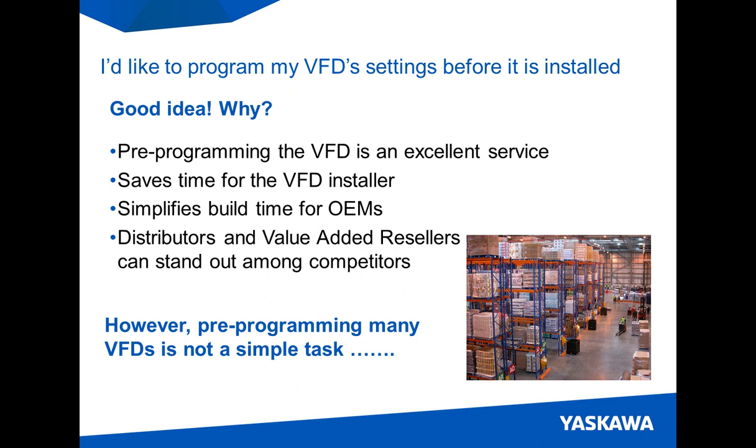So one of the things that I'm really excited to talk to you about in this next topic is a VFD, having hundreds of settings and parameters, making it capable of a wide variety of applications, being able to set up that VFD for installation in a comfortable environment without the time pressures we often encounter during installation. That could be a huge benefit. So pre-programming that VFD before it's installed actually makes a lot of sense for many reasons.